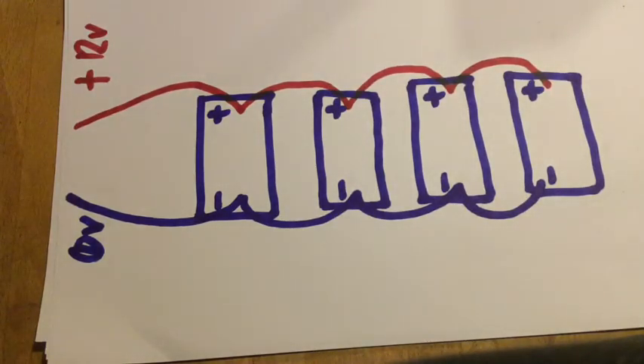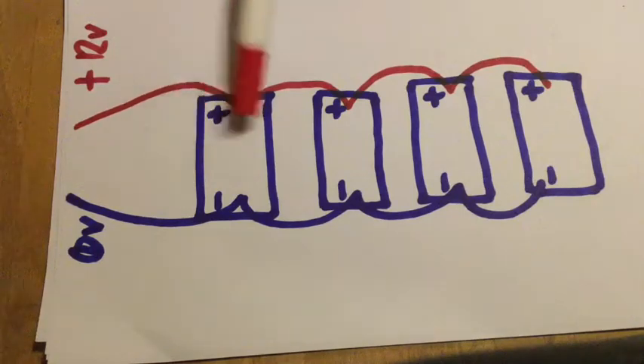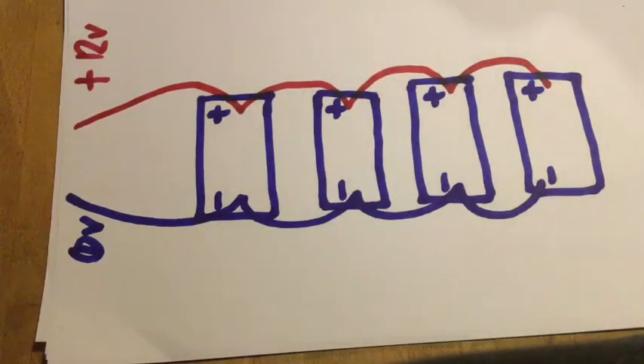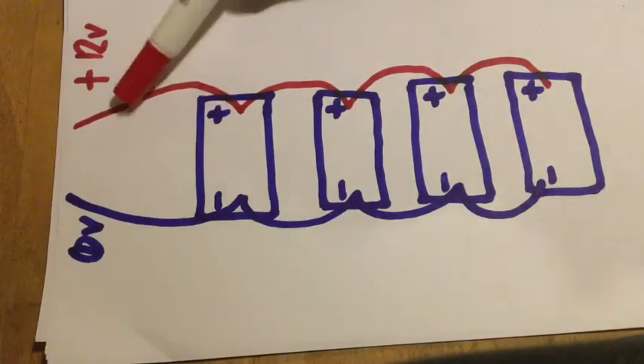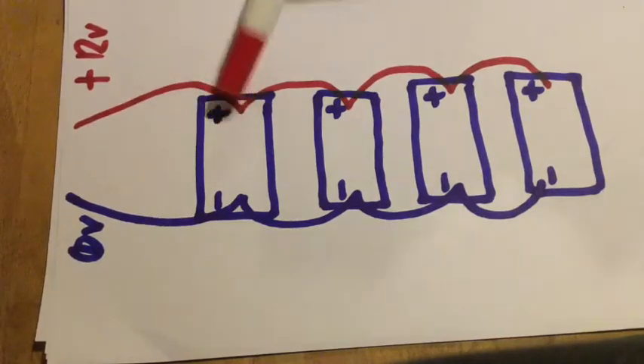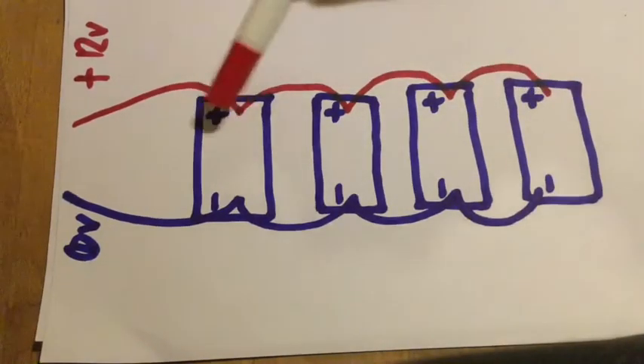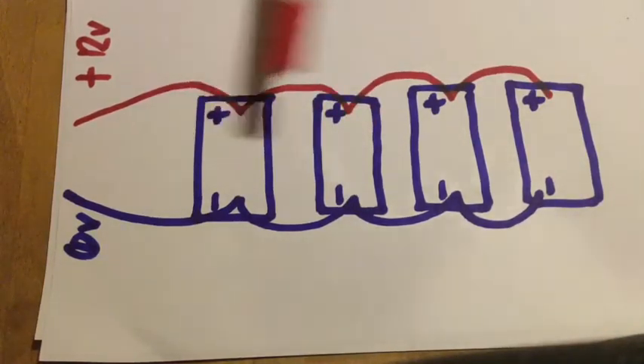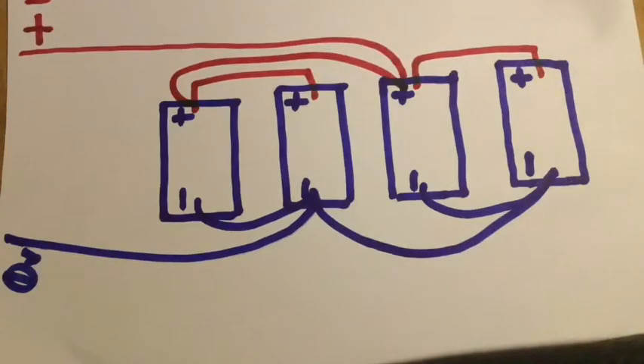If you've got lead-acid type batteries where you have to top them up with water, this one's going to boil or go dry a lot quicker than the one at the bottom. What you could do to sort of balance it out a bit better is you could swap this cable down to this end, so you'd have daisy chains. Then what you find is these two are balanced and these two are balanced, but all four aren't actually balanced together.